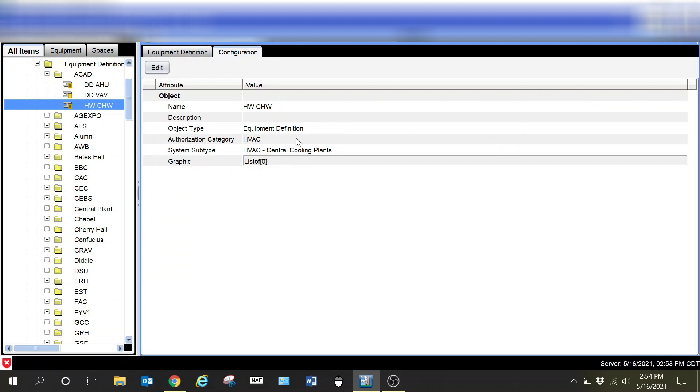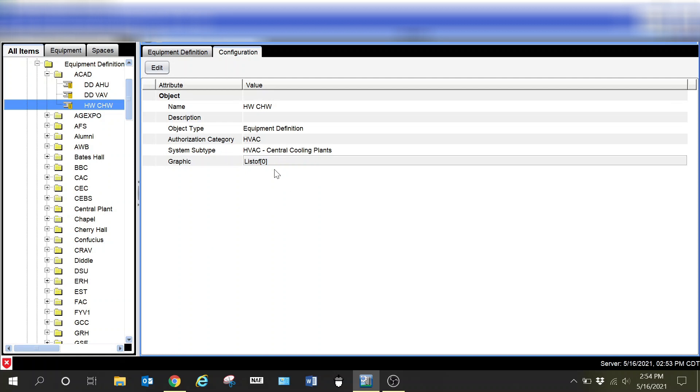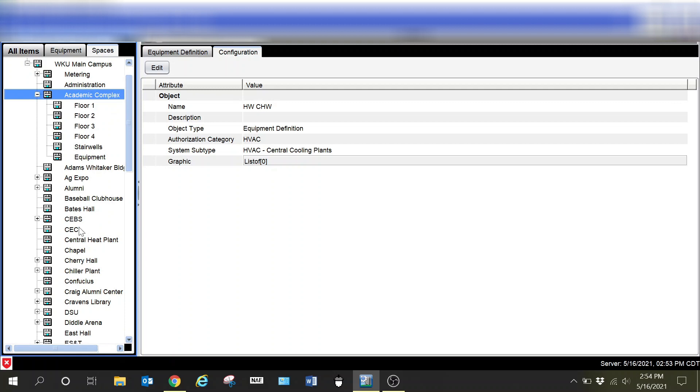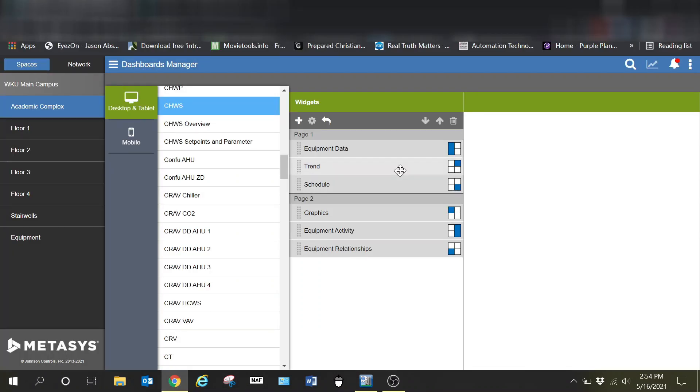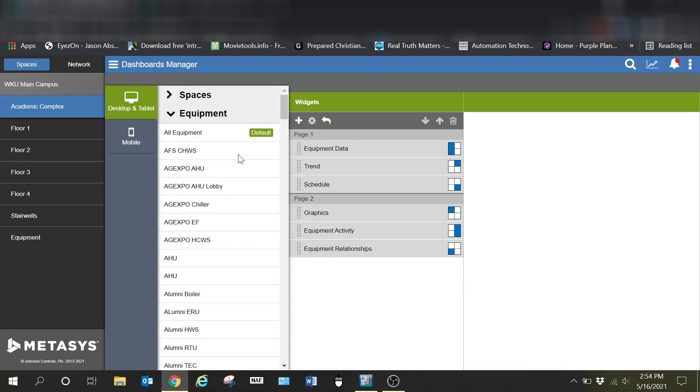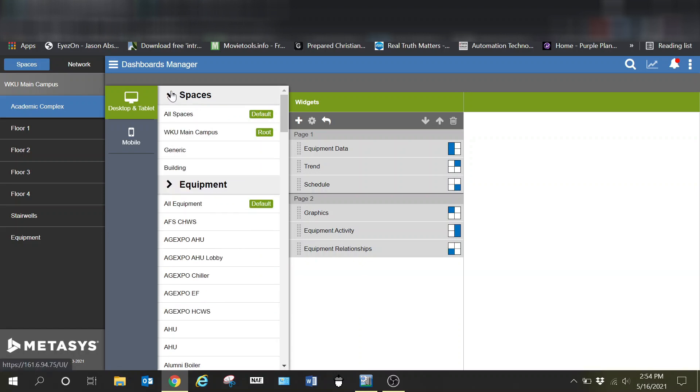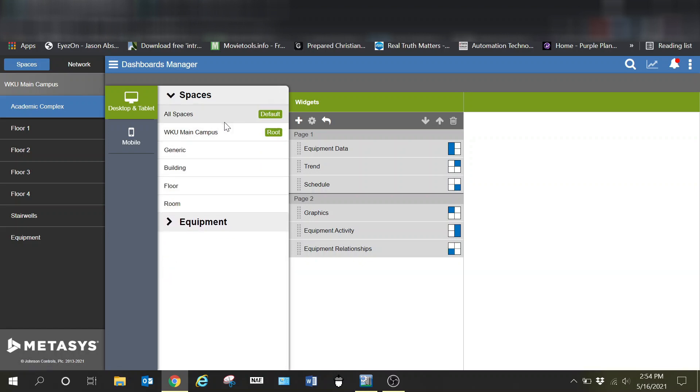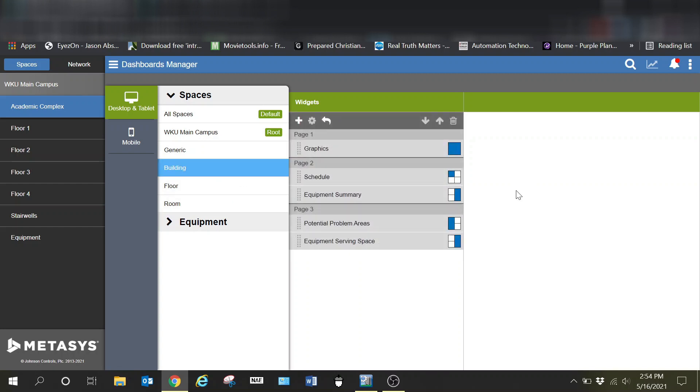All of this is something that can easily be overlooked when you're setting up MUI, especially if you get into just leaving everything as a default. You really need to go back in and change these to give them a little bit better identification as to what they are, particularly when you get into the spaces. When you're setting up spaces in MUI, a lot of the way your system looks is going to depend on how you select those particular devices and how you set them up, whether you set them up as generic, whether you set them up as a floor space, a room, or whatever.